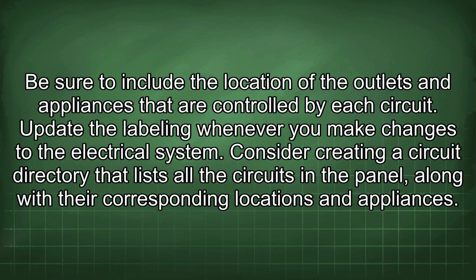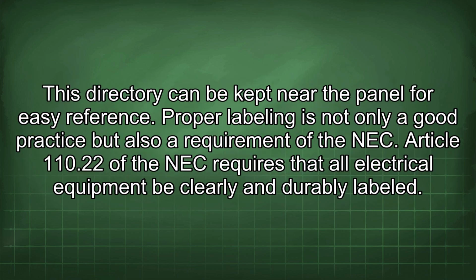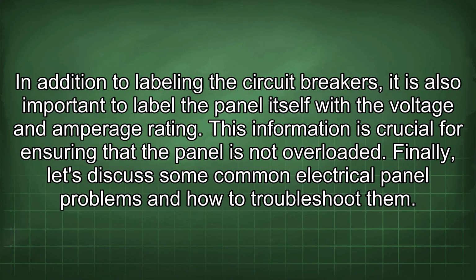Consider creating a circuit directory that lists all the circuits in the panel along with their corresponding locations and appliances. This directory can be kept near the panel for easy reference. Proper labeling is not only a good practice but also a requirement of the NEC. Article 110.22 of the NEC requires that all electrical equipment be clearly and durably labeled. In addition to labeling the circuit breakers, it is also important to label the panel itself with the voltage and amperage rating. This information is crucial for ensuring that the panel is not overloaded.